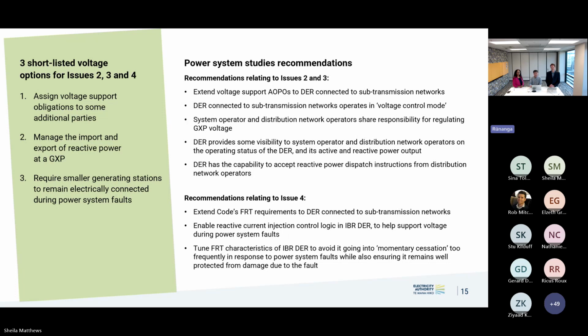And the basis for this from the system operator study is that if we can keep these plants supporting voltage, that will have a significant benefit in terms of managing voltage on the transmission network. The other recommendation here is that we have these plant operating in voltage control mode, which means that they maintain their voltage at their point of connection to the distribution network as there are movements in network voltage.